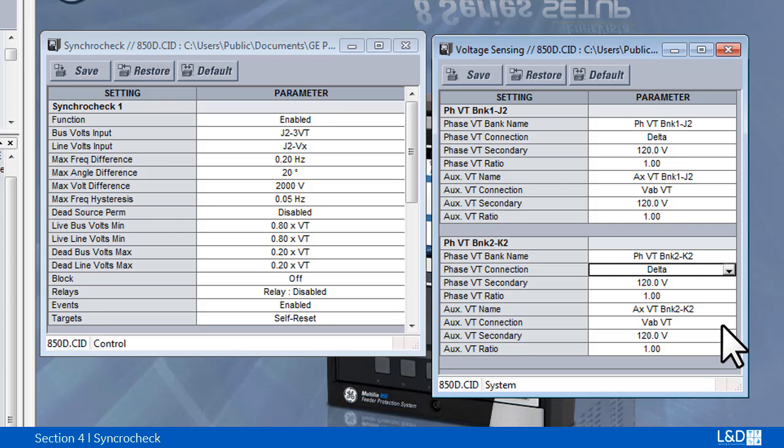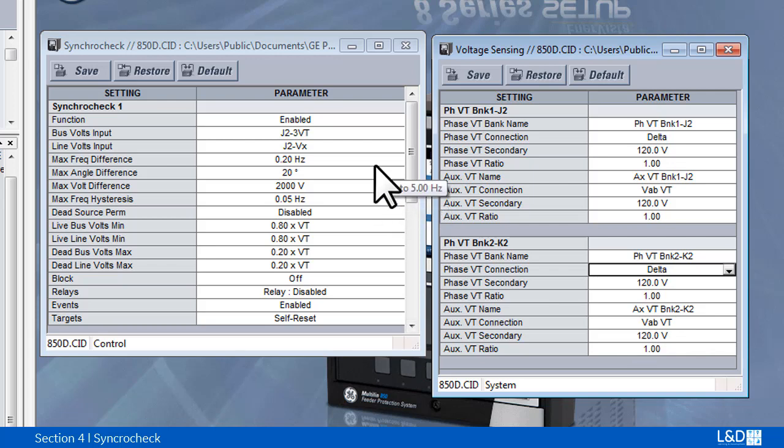Synchro check verifies that the voltage of the bus and line on the two sides of the supervised circuit breaker are within the set limit of magnitude, angle, and frequency difference.